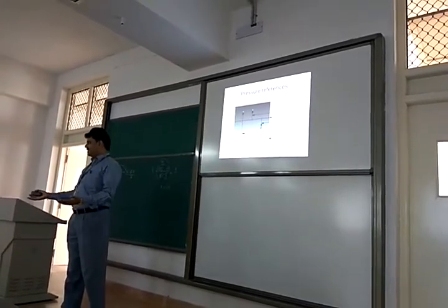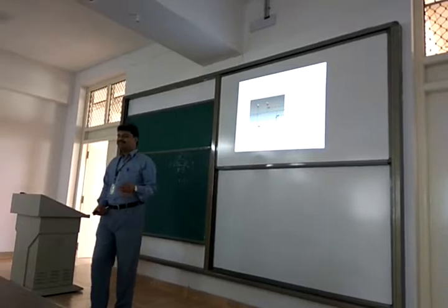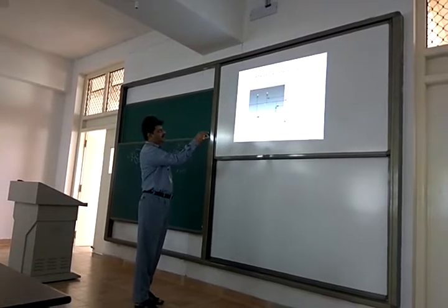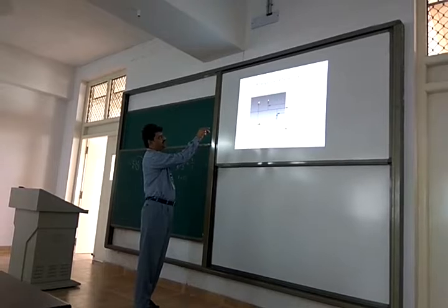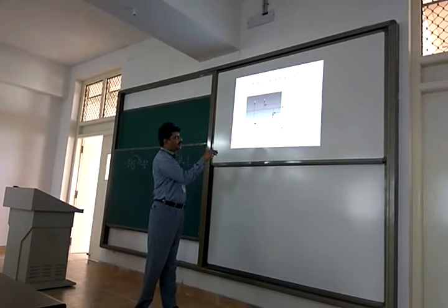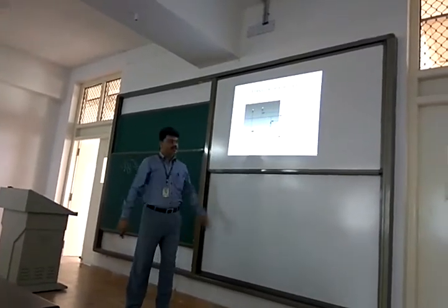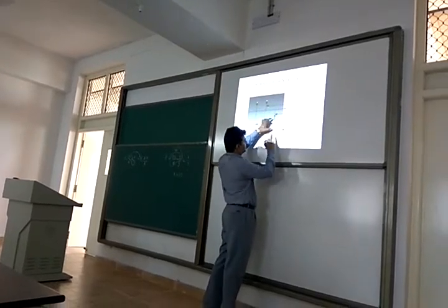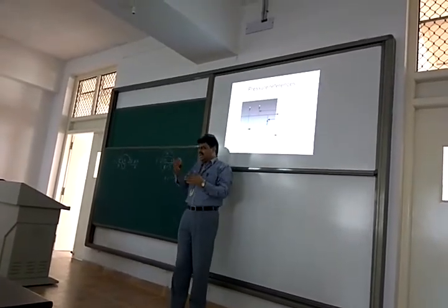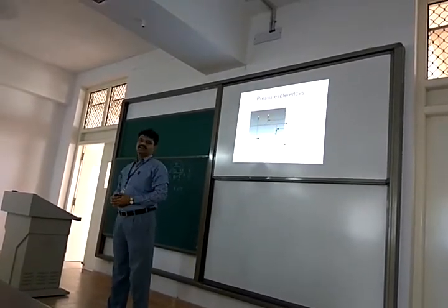Normally, Bourdon gauges and other pressure measuring gauges that we use, most of them will give you gauge pressure. If you have gauge pressure and want to know the absolute pressure, you add the atmospheric pressure to the gauge pressure, and you get the corresponding absolute pressure. If you have vacuum pressure from atmospheric pressure, you subtract the vacuum pressure, and you get the absolute pressure. This is atmospheric pressure, this is vacuum pressure, this is absolute pressure, for pressures below atmospheric pressure. Okay, it's simple arithmetic that you can remember and apply. Write your own formula and then get the actual value.